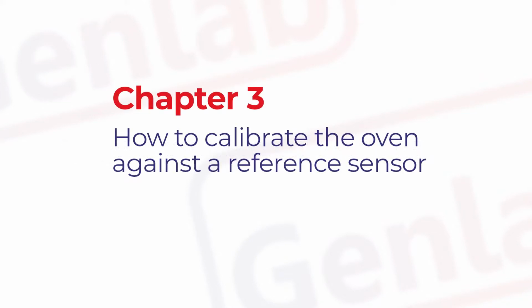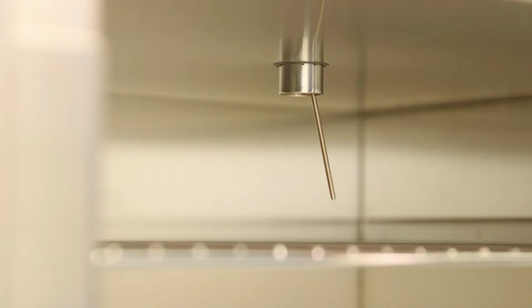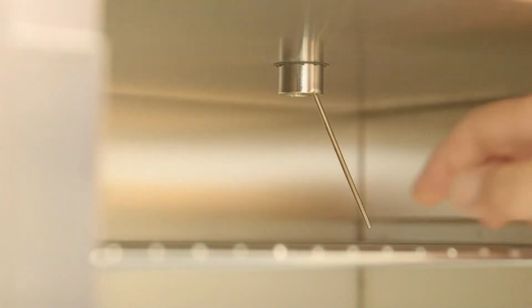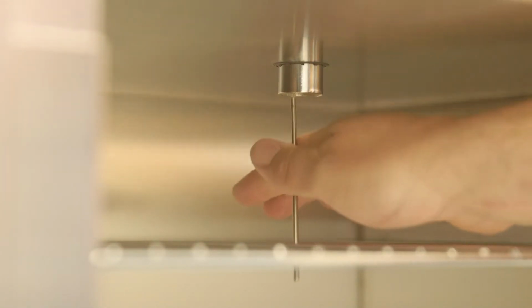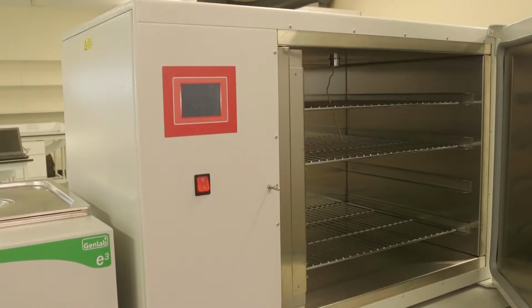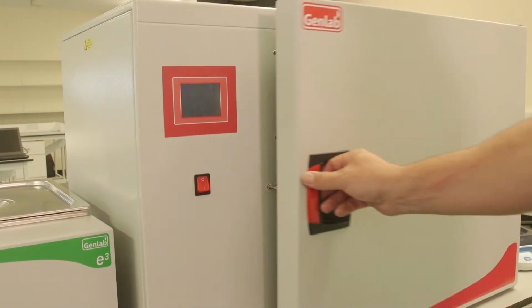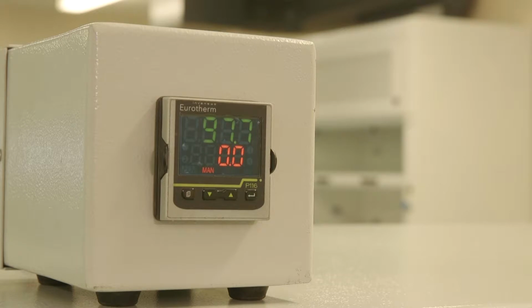This chapter is on how to calibrate the oven against a reference sensor. All ovens are set calibrated to the center point of the chamber. Over time, temperatures may drift, or if new probes are installed, or you may wish to make the oven display the same value as another external recording device.